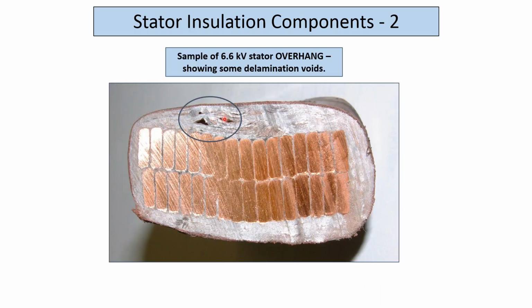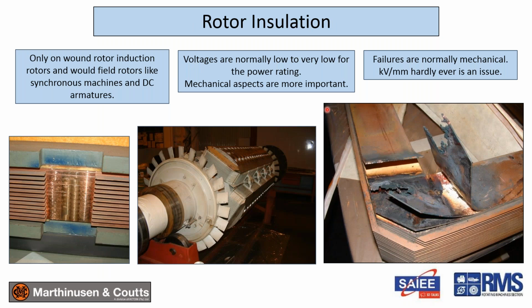So then this is an example of a high voltage failure, and very importantly, it's the overhang. It's not the slot portion. So you can have these imperfections. This doesn't mean it's a terrible winding or anything, but these are voids that you get from delamination. Now these would discharge, even though the main insulation doesn't discharge. You can see that this is a 6.6 kV machine. Because it's the overhang, the insulation looks a lot thicker than the samples that you'll see later that are taken from the slot.